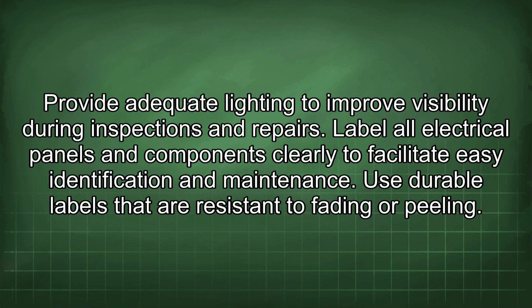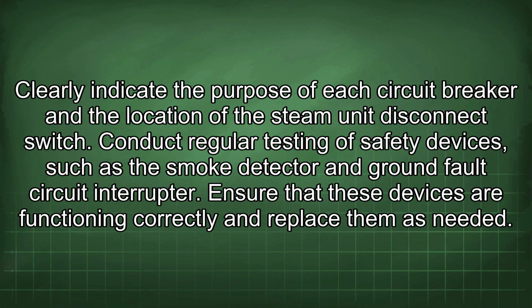Label all electrical panels and components clearly to facilitate easy identification and maintenance. Use durable labels that are resistant to fading or peeling. Clearly indicate the purpose of each circuit breaker and the location of the steam unit disconnect switch. Conduct regular testing of safety devices, such as the smoke detector and ground fault circuit interrupter. Ensure that these devices are functioning correctly and replace them as needed.